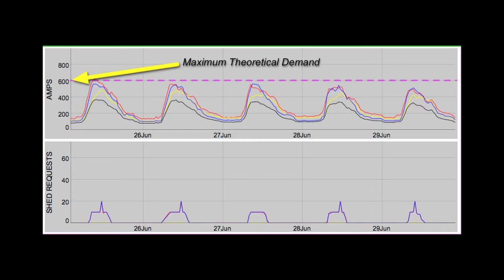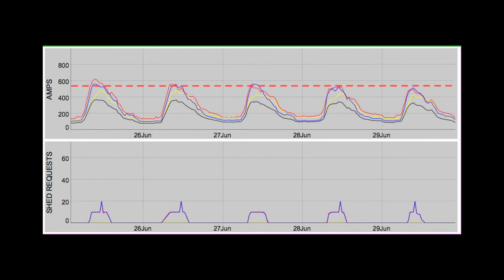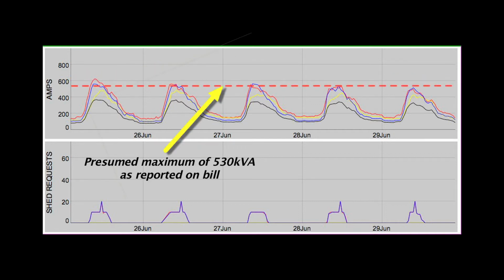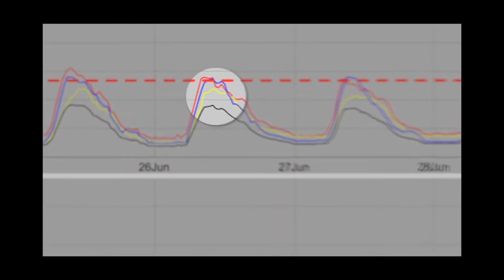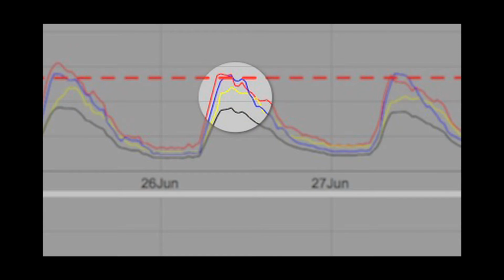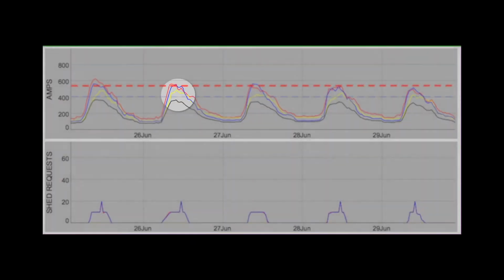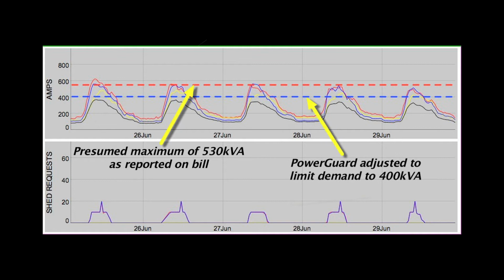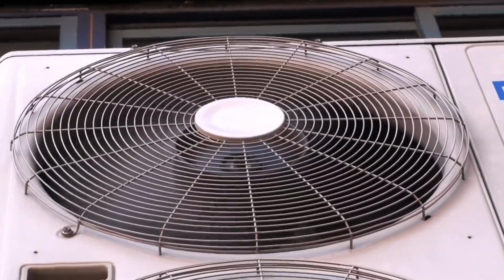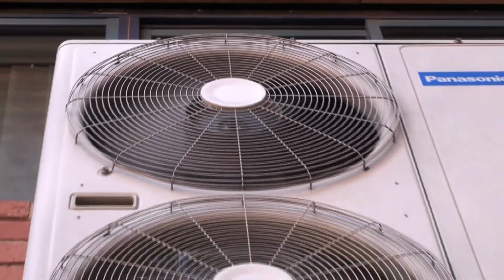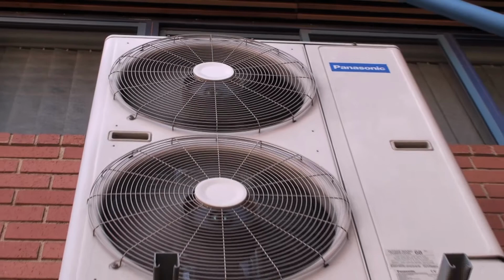The maximum theoretical demand at this particular client is 600 kVA, but we will use 530 kVA since that is a figure that has been reported on their bill. That is represented by this dotted red line, and the further we keep the black line from here, the greater the saving. In this instance, we adjusted PowerGuard to limit the demand to 400 kVA, and that is represented by this dotted blue line.